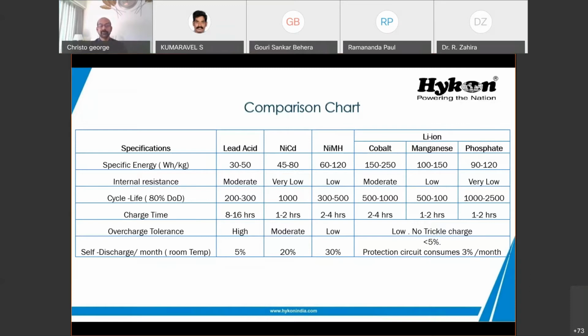The specific energy, if it is 30 to 50 for lead acid, it means that if we have a lead acid 100 Ah battery, in lithium battery you can see the specific energy per kg is much higher. So it's almost half. If a 100 Ah lead acid battery weighs 50 kg, the same lithium battery of 100 Ah will have only half of it, that is 25 kg. So 50% of the weight will come down, as well as one third of the size will also come down in lithium battery. And internal resistance is very low for LFP. That's why the cells are not getting heated up when heavy current flows. Normally, in other lithium batteries the internal resistance is higher than lithium phosphate, so the heating will be more.